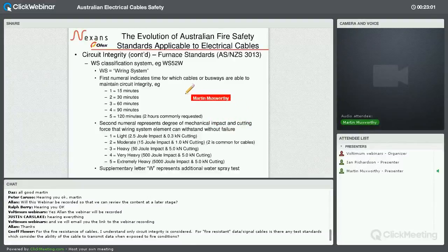Just to run down a quick summary of how 3013 defines the wiring system classification, and people that have used fire-rated cables would be familiar with this. I use the example of WS52W, and that's what most fire-rated cables comply with. That means a 120 minute or 2 hour fire test, an impact and cutting test of rating 2, which is, I guess, what is deemed to be most common for, say, polymer cables, plastic or XLPE insulated cables, for example. And then the W means a supplementary water test has been applied to the cable.